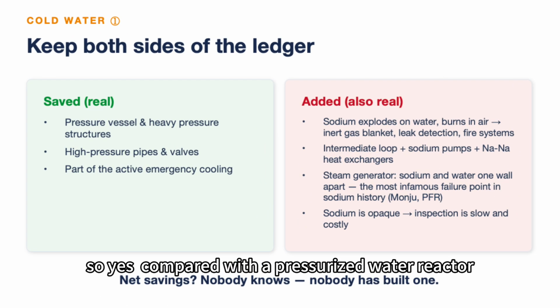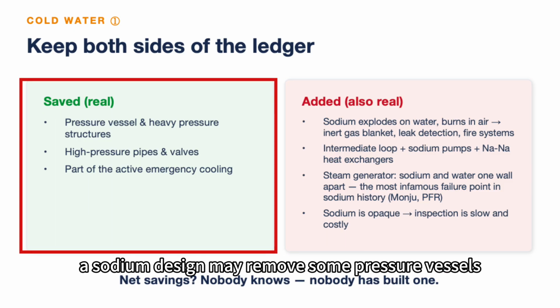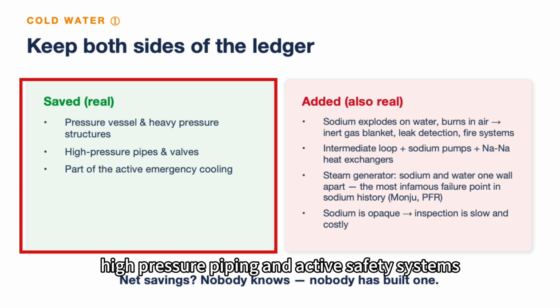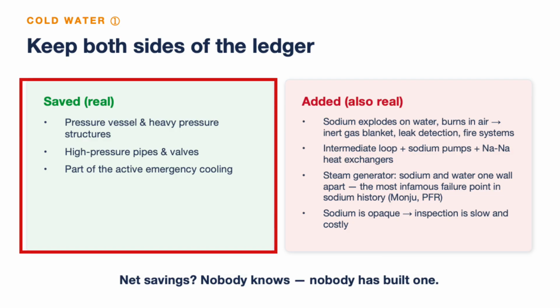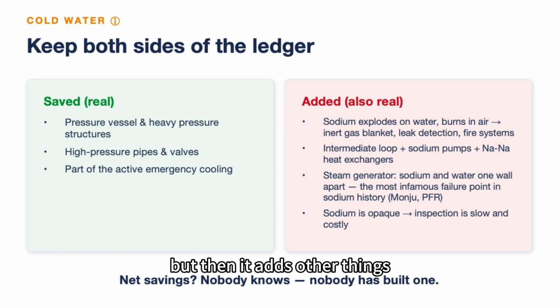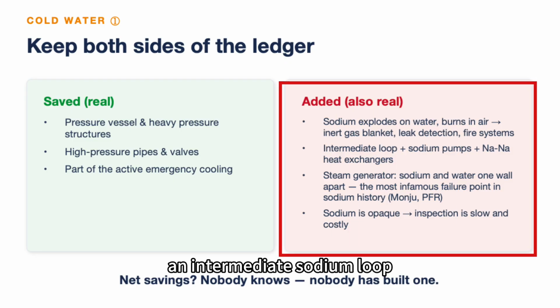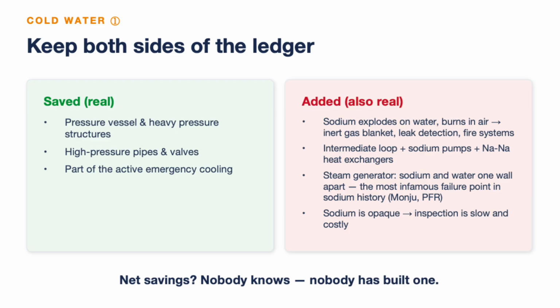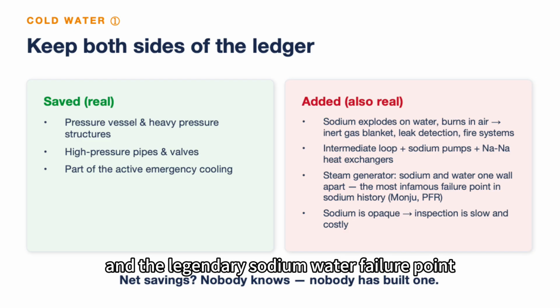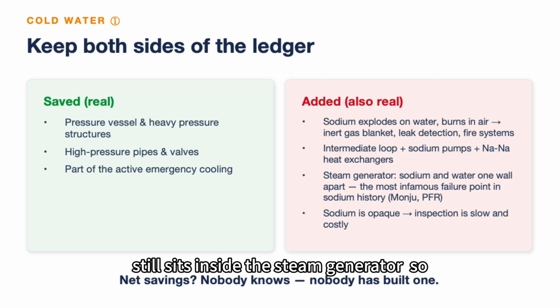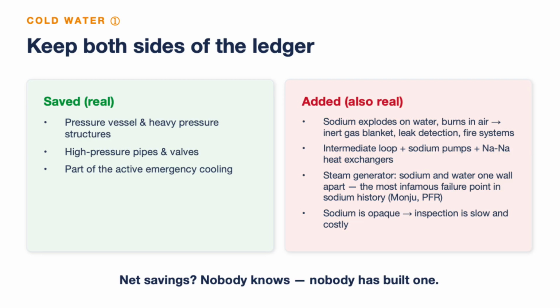So yes, compared with a pressurized water reactor, a sodium design may remove some pressure vessels, high-pressure piping, and active safety systems. That part is real. But then it adds other things: an intermediate sodium loop, sodium pumps, sodium-to-sodium heat exchangers, inert gas protection, leak detection systems, fire suppression systems, and the legendary sodium-water failure point still sits inside the steam generator. So you remove old equipment, and then you add new equipment. This is not magic. This is engineering.